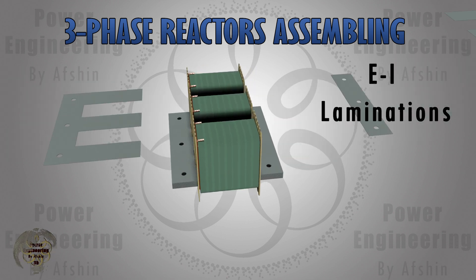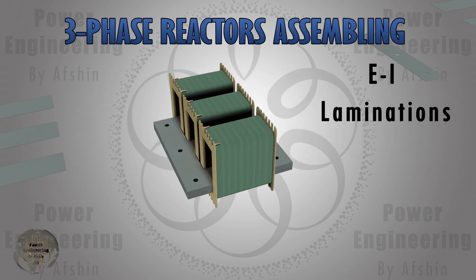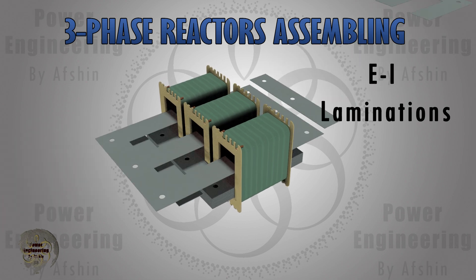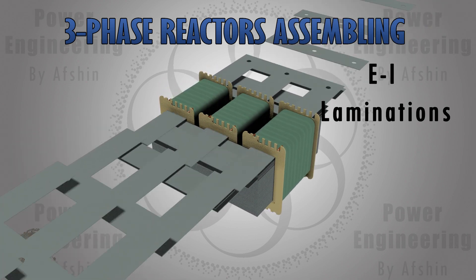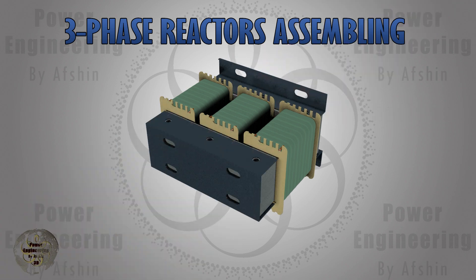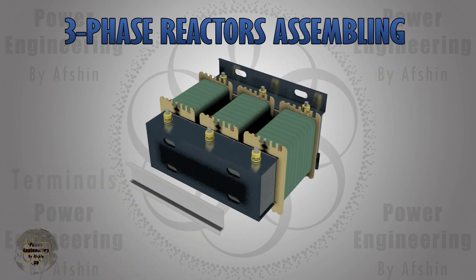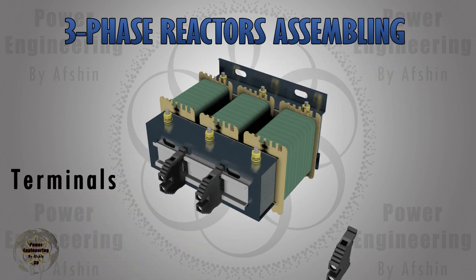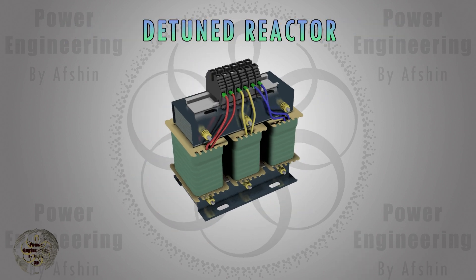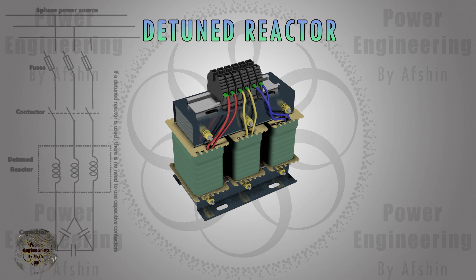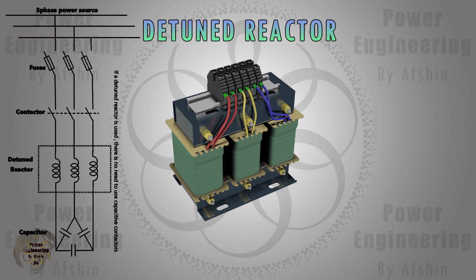While observing the assembly process, you will receive brief explanations of each filter type. We will start with an introduction to the detuned reactor. A detuned reactor is a specialized type of inductor used in power factor correction (PFC) systems, particularly in conjunction with capacitor banks. Its primary purpose is to avoid resonance conditions that can occur when capacitor banks are installed in electrical systems with significant harmonic distortion.